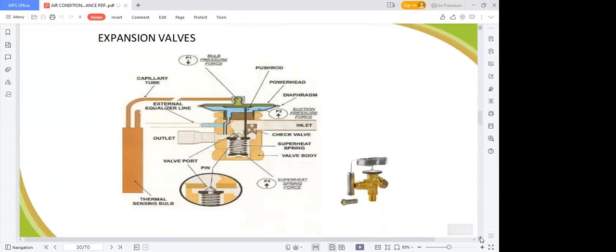Then your expansion valve, this is how it looks. The essence of the expansion valve is to reduce pressure coming from the refrigerant gas. And it's always between the condenser coil and the evaporator. It is very important that your installation is done well while this is installed. If your installation is not done well, you see that the copper pipes are thin. This is actually zoomed, this is how it looks. You see these things you are seeing, they are very thin. When you do your installation and you have a lot of dirt within your system, those dirt can actually block it. And if they block it, it will affect every component of the equipment. The equipment will not bring out the required cooling.